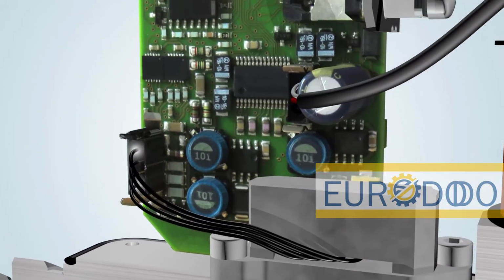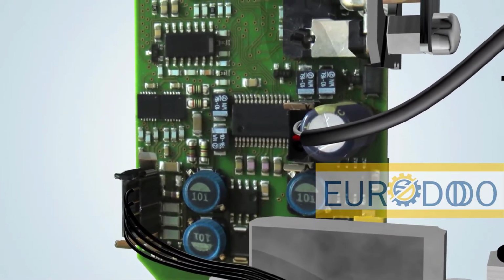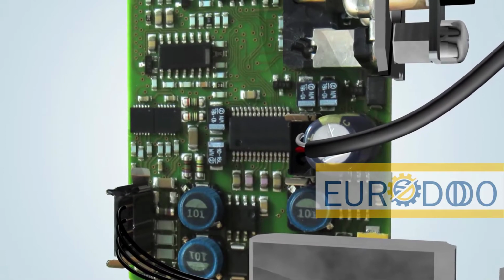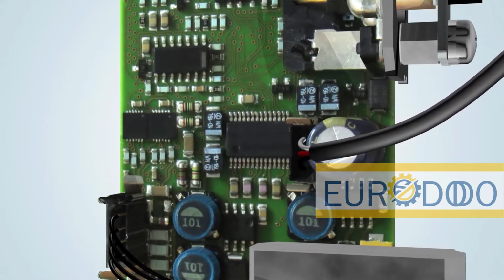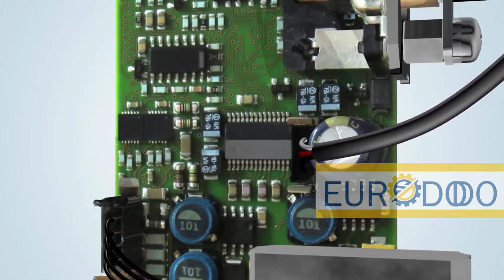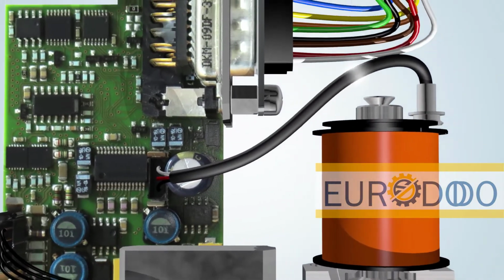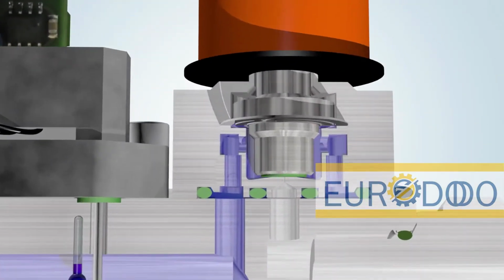This signal is forwarded to the microprocessor. The instrument receives a set point via the PC, PLC or analog port. This required value is compared with the measured value. If the required value is higher than the measured value, the PID controller will actuate the control valve.